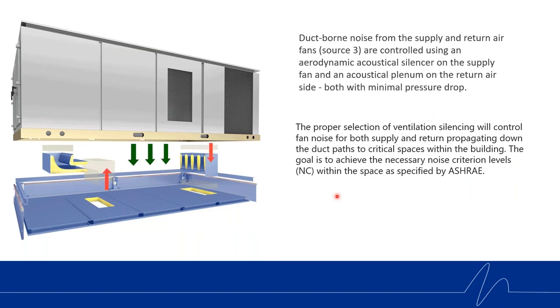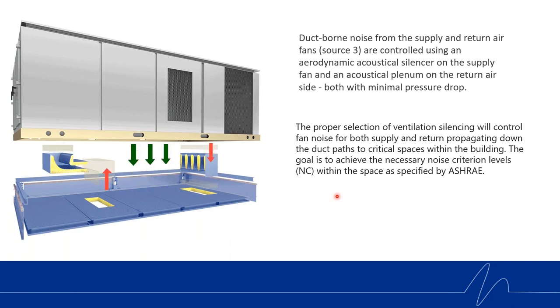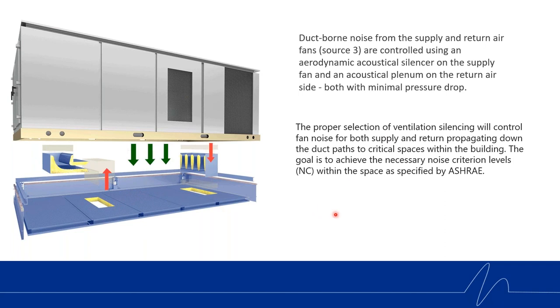For ductwork and duct-borne noise — source three — duct-borne noise from the supply and return air is controlled by using aerodynamic acoustical silencers on the supply fan and an acoustical plenum on the return air side. We try to fit those within the roof curb to make a compact unit of noise control, achieving that with minimal pressure drop. The proper selection of ventilation silencing will control fan noise for both supply and return, propagating down the duct paths to critical spaces within the building. The goal is to achieve the necessary noise criterion NC levels within the space as specified by ASHRAE. These silencers and plenums are often custom-designed based on project-specific location.